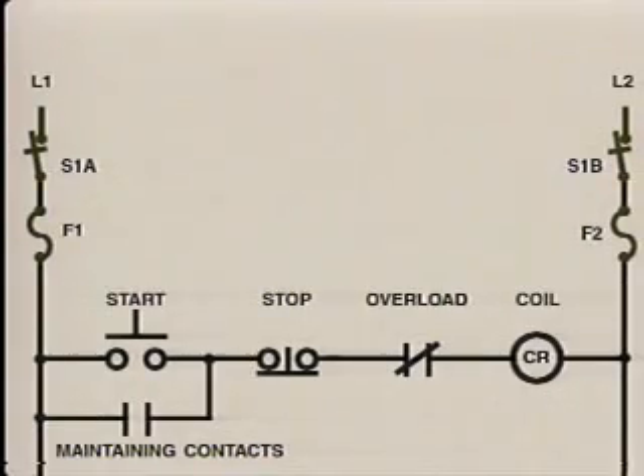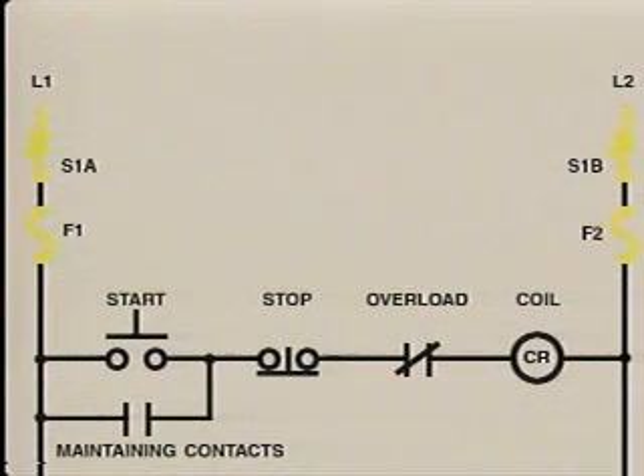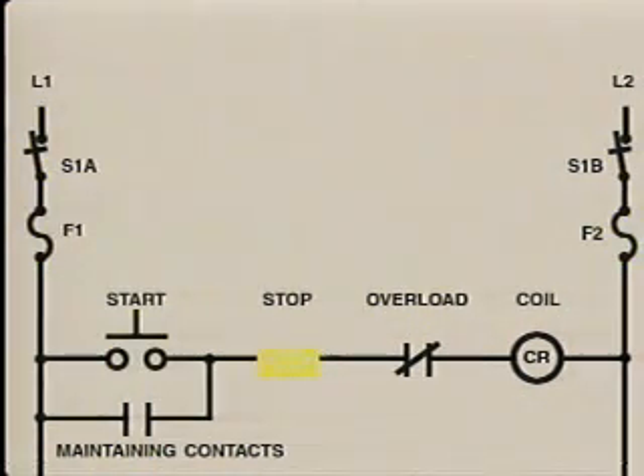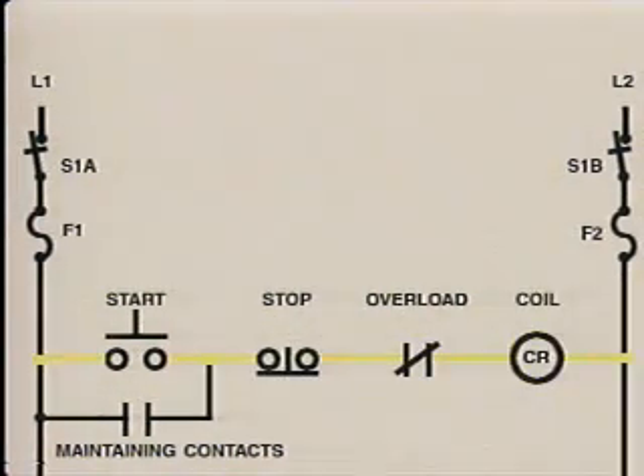In this example, the power switch components and the fuses have already been eliminated as possible causes of the problem. The remaining possibilities are the start switch, the stop switch, the overload contacts, the control relay's coil, and the wiring that connects these components to each other and to the circuit's operating voltage.